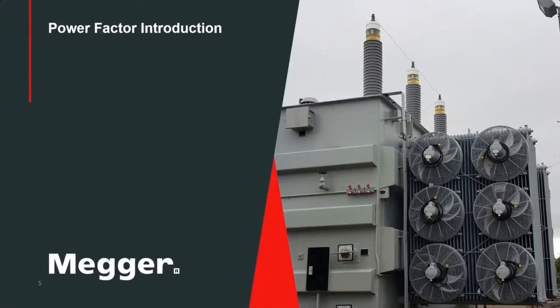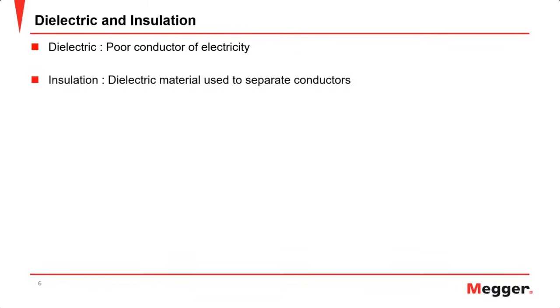Next, introducing power factor. For those of you here who are new to the industry or trying to gather some basic information on how power factor is used to evaluate insulation, we first want to start off with some definitions here of what is a dielectric and what is insulation. So the dictionary definition of a dielectric is something that is a poor conductor of electricity. So you would think this would be silicone, rubber, or wood. Insulation is dielectric material that is used to separate conductors. So this would be the wood inside of a transformer or the paper that is wrapped around the coils that helps to keep those conductors separated. And it's important to note that the conductors can be at the same potential or different potentials.